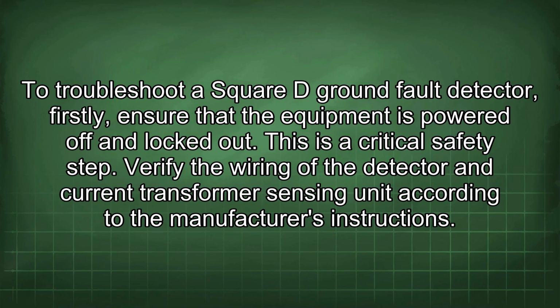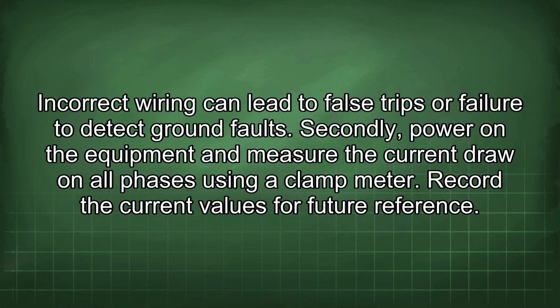To troubleshoot a Square D ground fault detector, firstly, ensure that the equipment is powered off and locked out. This is a critical safety step. Verify the wiring of the detector and current transformer sensing unit according to the manufacturer's instructions. Incorrect wiring can lead to false trips or failure to detect ground faults.